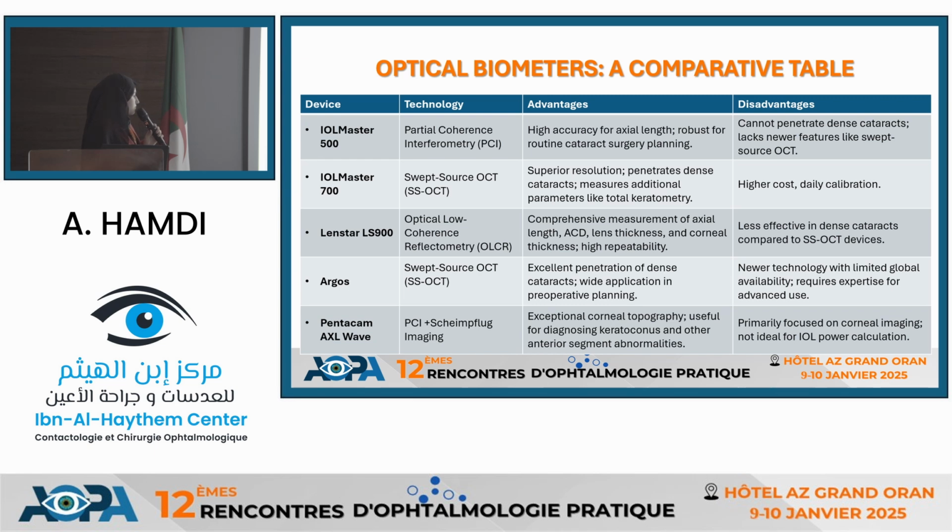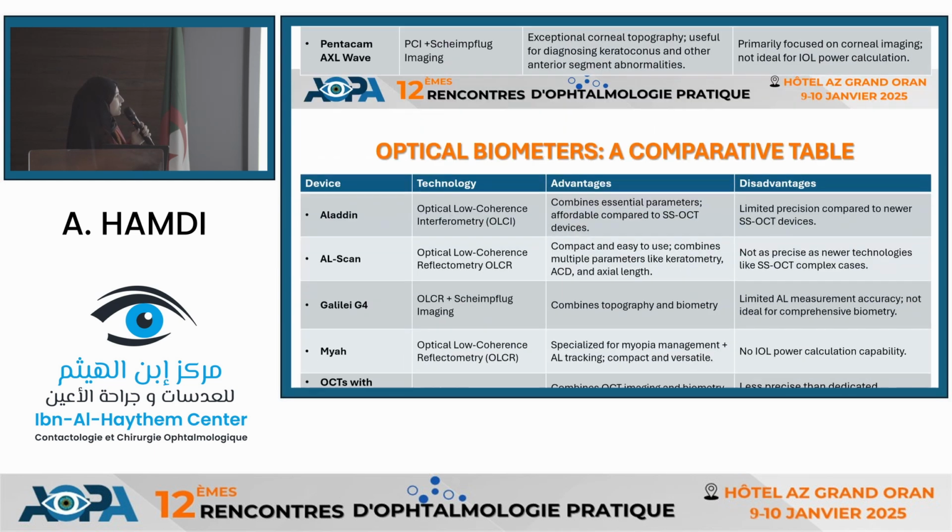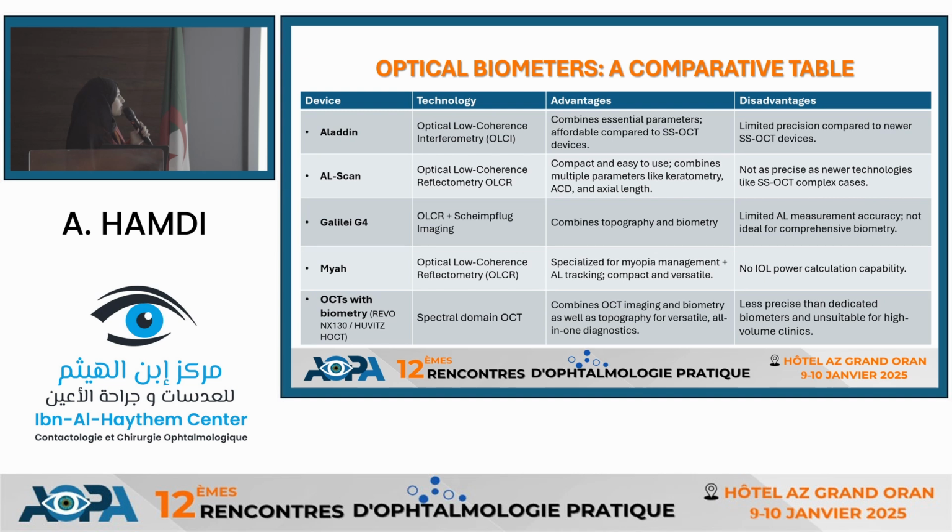Pentacam AXL Wave, Scheimpflug imaging with interferometry. So it's very exceptional for corneal topography and corneal diseases diagnosis. But it's primarily used for corneal imaging and not for IOL calculations. Aladdin combines essential parameters. It's very affordable. However, it has limited precision in IOL calculations. Same goes for AL-Scan.